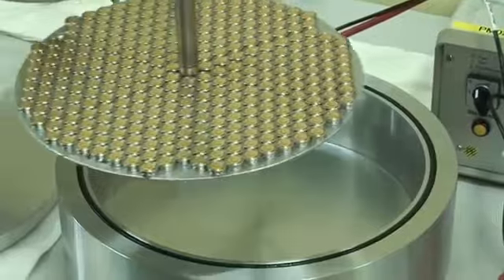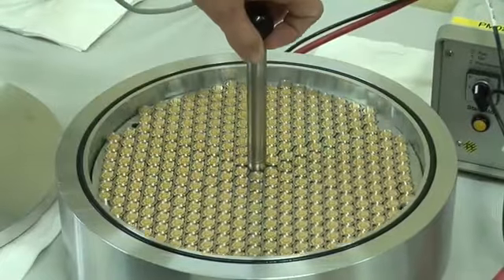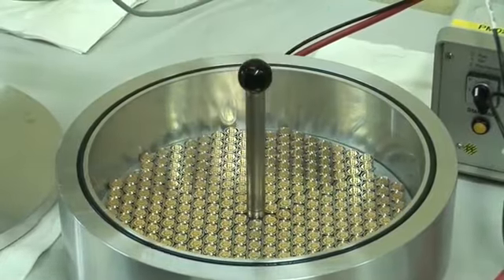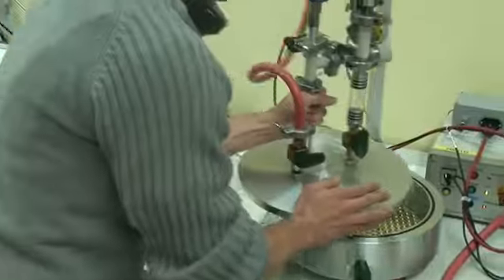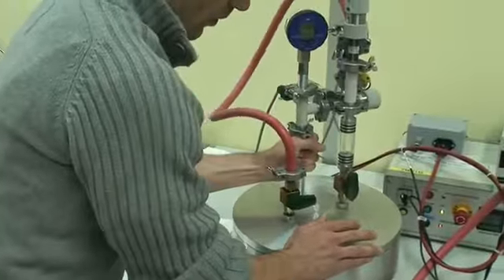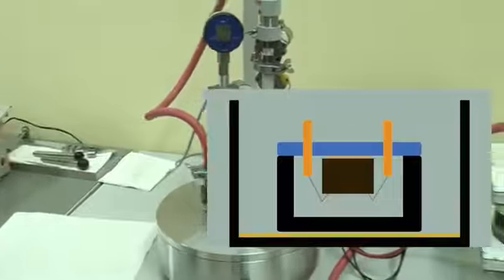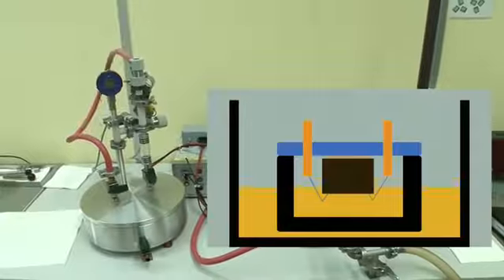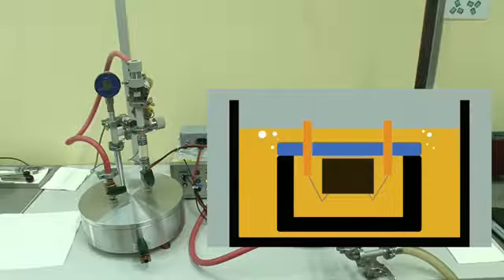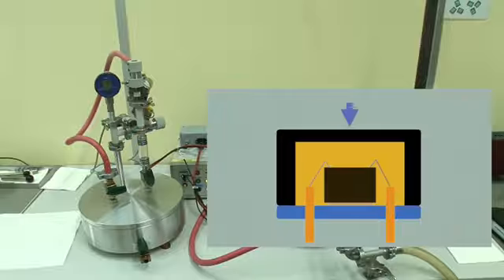The inside of the pressure transducer, which at this point is still full of air, is now filled with oil. To prevent any measurement errors occurring as a result of air bubbles in the oil, for example, the pressure transducers are filled with oil using a special technique that lasts around 12 hours. Filling with oil means that pressure is now transferred directly from the steel membrane to the sensing element.